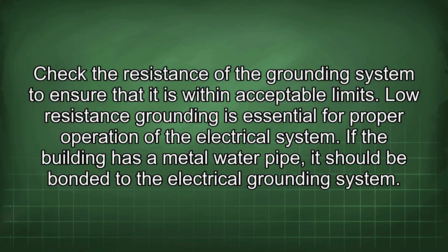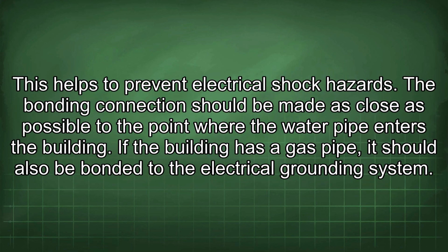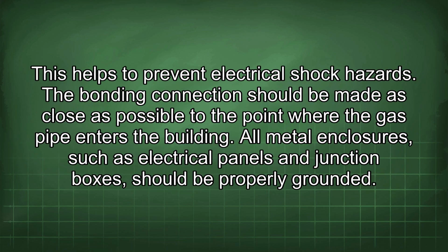If the building has a metal water pipe, it should be bonded to the electrical grounding system. This helps to prevent electrical shock hazards. The bonding connection should be made as close as possible to the point where the water pipe enters the building. If the building has a gas pipe, it should also be bonded to the electrical grounding system. This helps to prevent electrical shock hazards. The bonding connection should be made as close as possible to the point where the gas pipe enters the building.